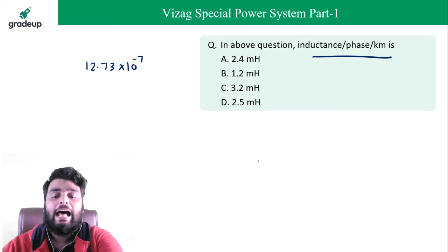So for an equilateral triangle, you have already found d, which is 282 centimeter, divided by r. This is the diameter given, so r dash will be 0.7788 multiplied by 1.24 by 2, which is 0.62. When you do the multiplication, I am getting 12.73 into 10 raised to power minus 7. And remember, this formula will give you the answer in Henry per meter.